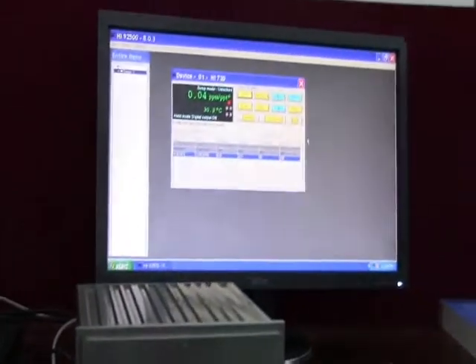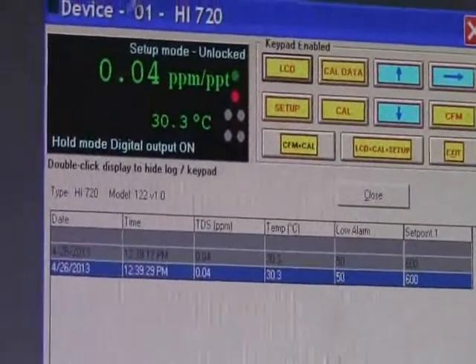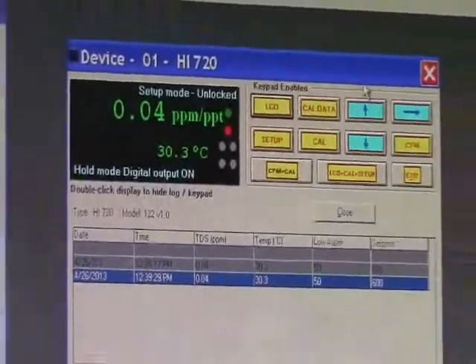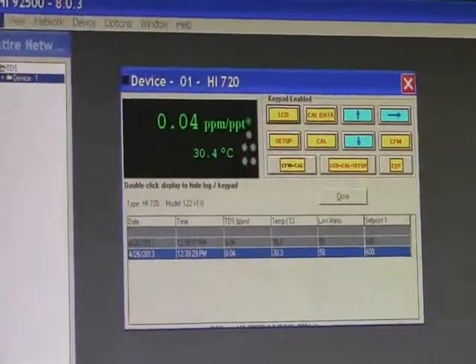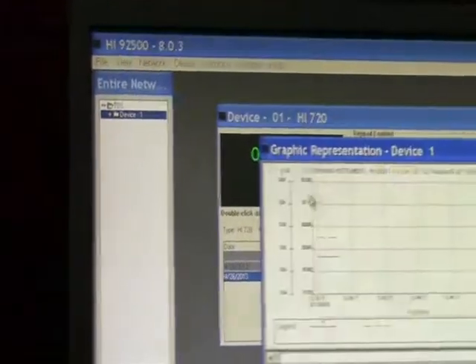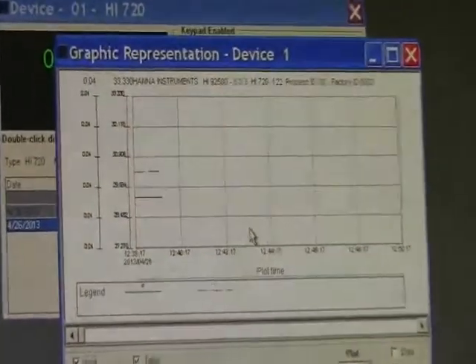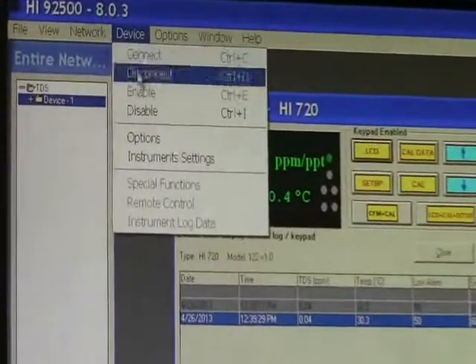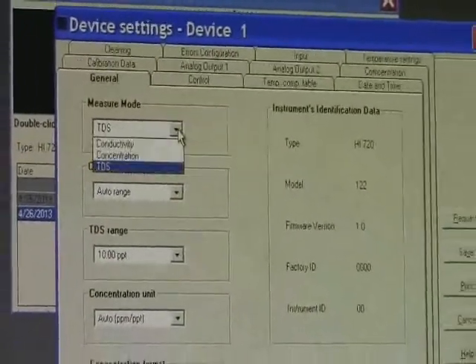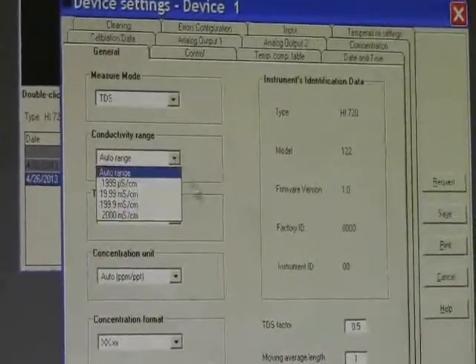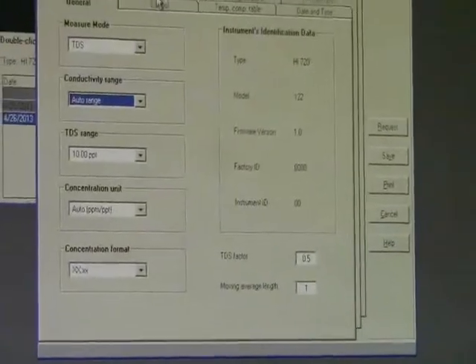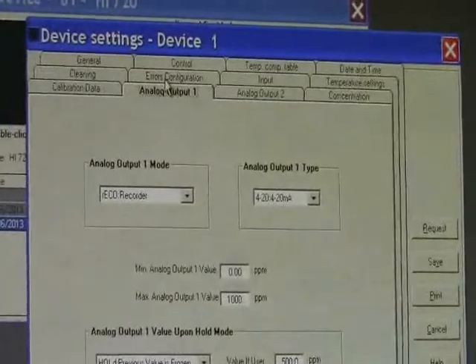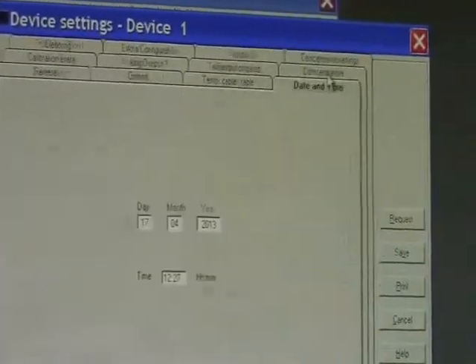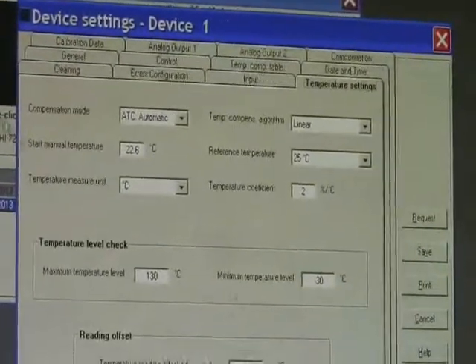Coming to the screen of the computer, the entire front panel of the controller is displayed as it is on the screen. The customer can do the settings and the changes even with the keypad on the screen. Having a look at the other options, the customer can get a graph of the values of TDS, conductivity and concentration. The device option will help you to get into instrument settings. These settings allow you to change the parameter between TDS, concentration, conductivity, change the range, and similarly other settings. All the settings of the analog output, input, date, time, and temperature are available in this window.